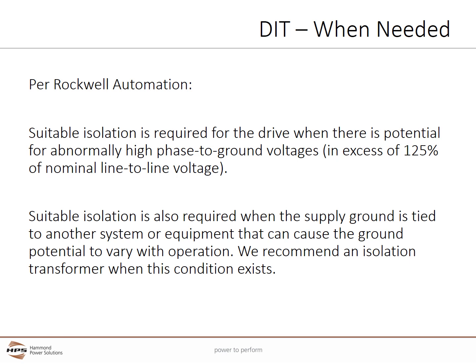Again, per Rockwell Automation, but this can be applied to other VFDs, suitable isolation is required for the drive when there is potential for abnormally high phase to ground voltages, which are in excess of 125% of the nominal line-to-line voltage. Suitable isolation is also required when the supply ground is tied to another system or equipment that can cause the ground potential to vary with operation. We recommend an isolation transformer when these conditions exist.